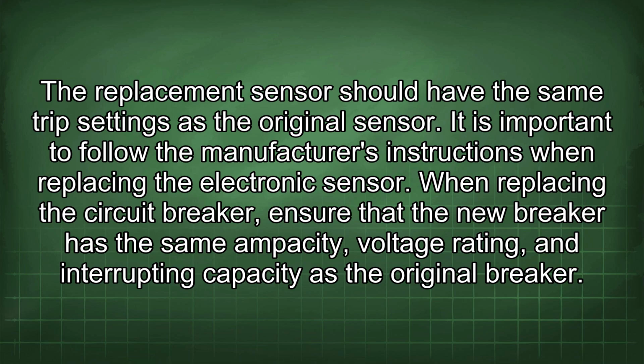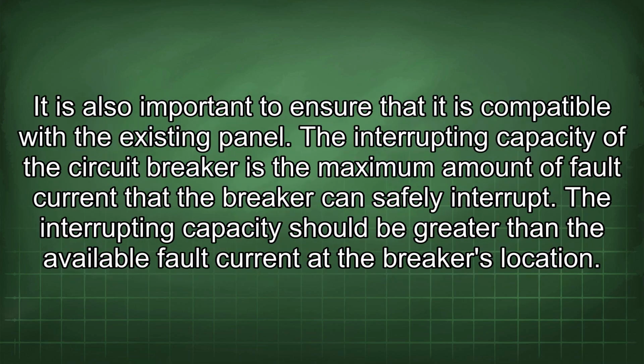When replacing the circuit breaker, ensure that the new breaker has the same ampacity, voltage rating, and interrupting capacity as the original breaker. It is also important to ensure that it is compatible with the existing panel. The interrupting capacity of the circuit breaker is the maximum amount of fault current that the breaker can safely interrupt. The interrupting capacity should be greater than the available fault current at the breaker's location.